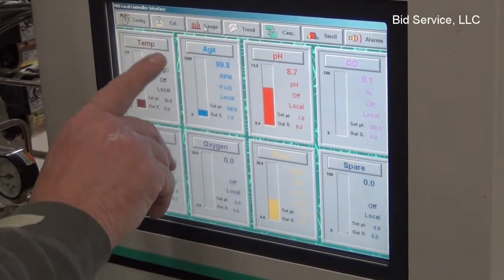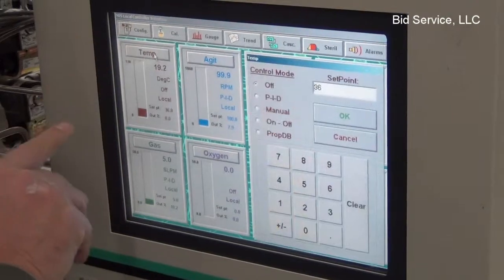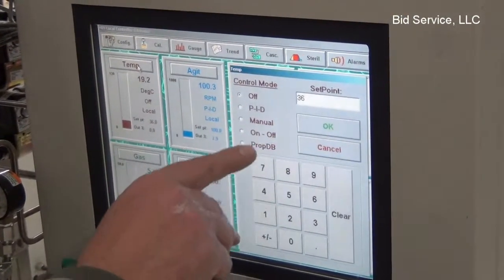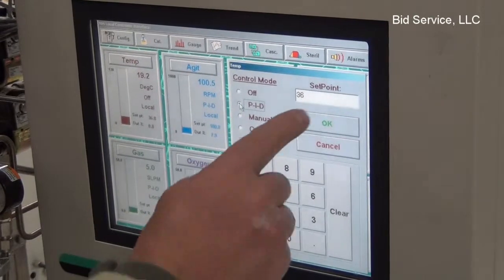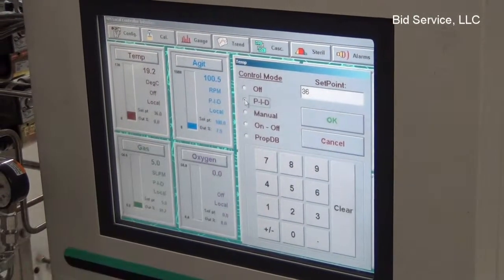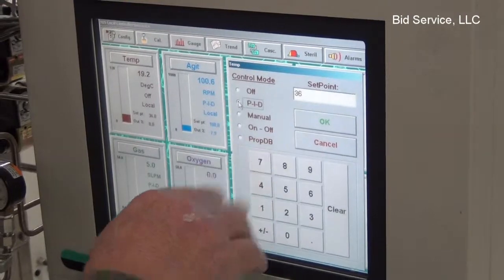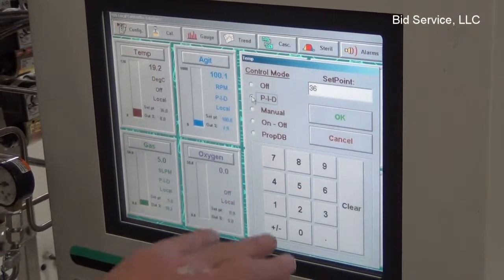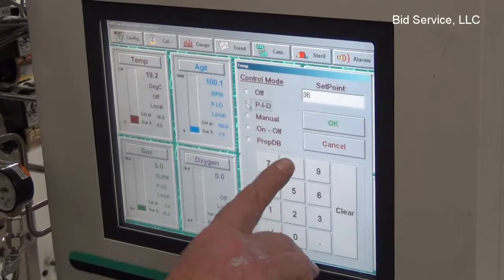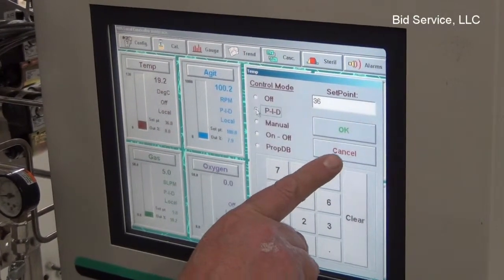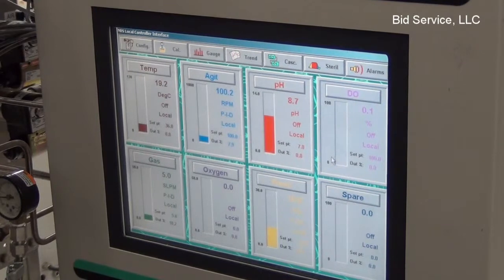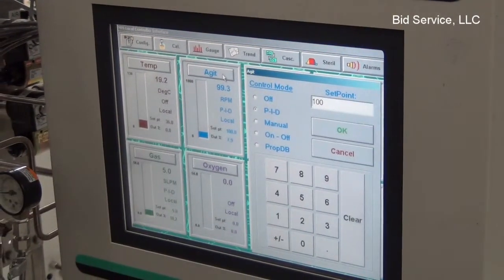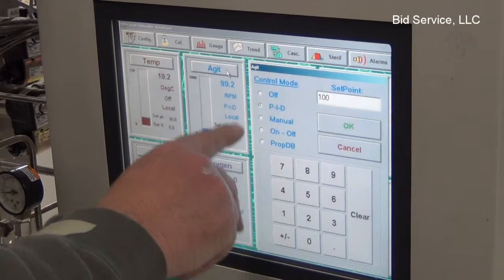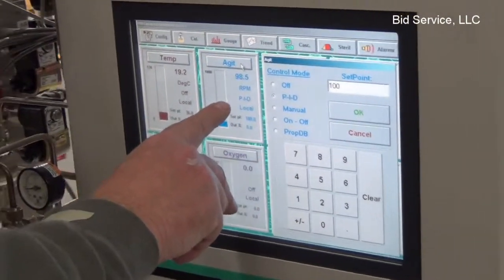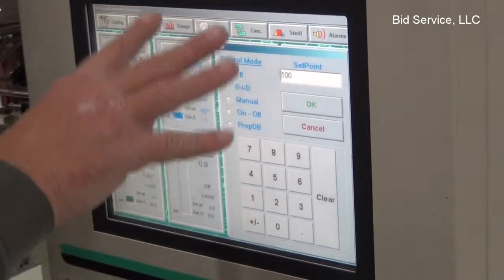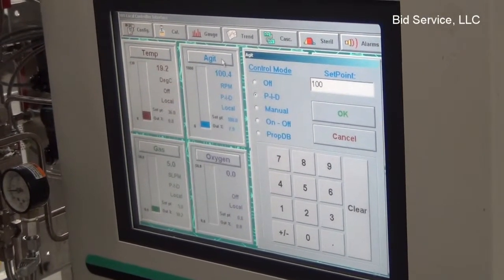This is your temperature. To change the temperature, you could go in and change it. I have it set for 36. Change it to PID, hit on, and it'll start ramping up the temperature. I've had it all the way up and it's calibrated and works fine. I will show you where the temperature thermocouple is on this in a minute. Here's your agitator for the stirrer that you saw inside there. You can see I have this on and it's set for 100, and at the same time you can see it's continually fluctuating, trying to maintain that 100 RPMs.